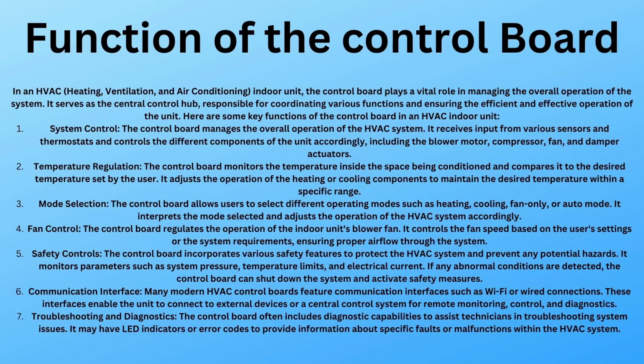Safety control. The control board incorporates various safety features to protect the HVAC system and prevent any potential hazards. It monitors parameters such as system pressure, temperature limits, electrical current. If abnormal conditions are detected, the control board can shut down the system and activate safety measures. So you have a blower motor that goes out. Some of them have a safety factor that kicks in and regulates a temperature, like through a thermostat probe on the board, and it can actually kick the system into a safe mode, and it'll flash. And these control boards will have a pattern on the door, and it'll flash a certain code, say 3 or 4. You can look over on your nomenclature that's on the panel, and it'll tell you what's going on. A blower motor failure.